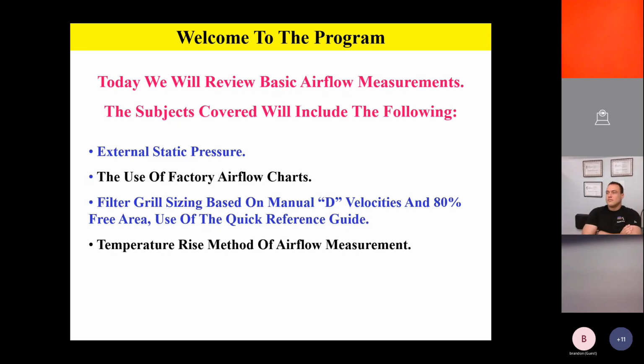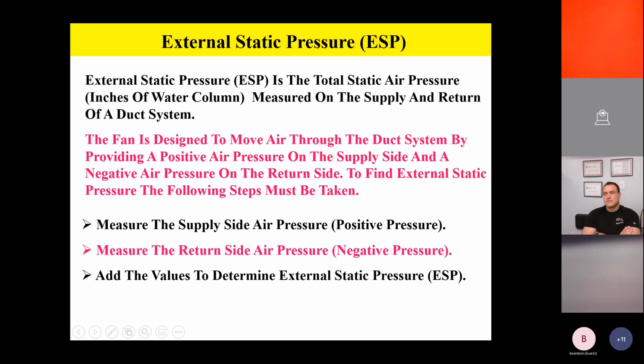Okay, so external static pressure is the total static or the total air pressure, in inches of water column, measured on the supply and return side of a duct system. Please remember, the fan is designed to move air through the duct system by providing a positive air pressure on the supply side and a negative air pressure on the return side. Now, to find external pressure, we're going to take the following steps. Number 1, we're going to measure the supply side air pressure, which is going to be a positive pressure, with the appropriate tools, and we'll talk about those tools in just a second.